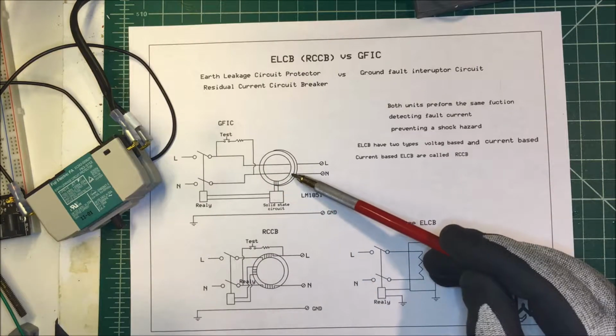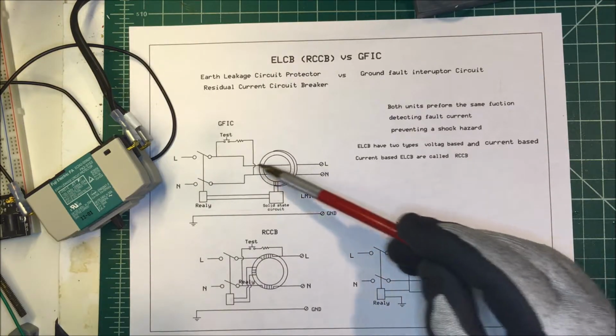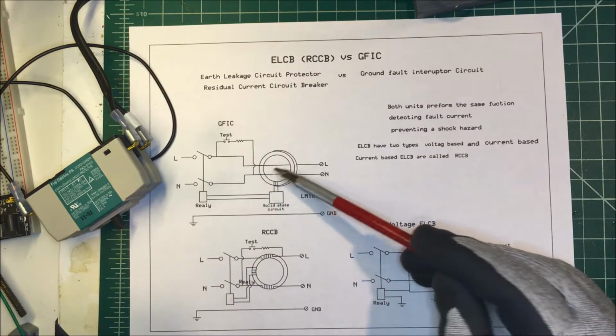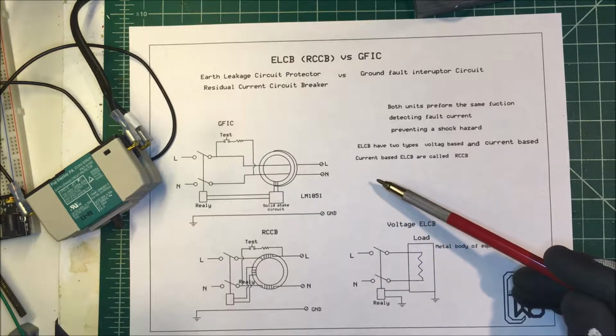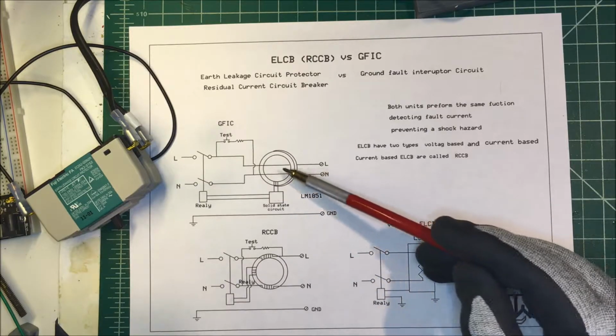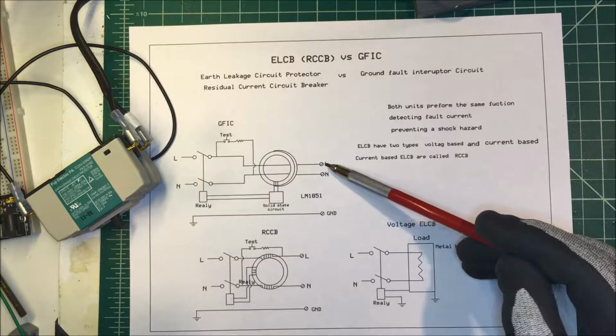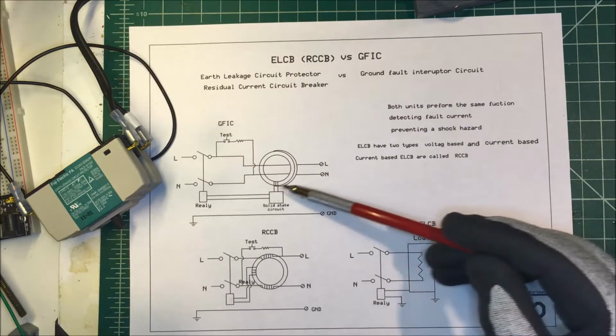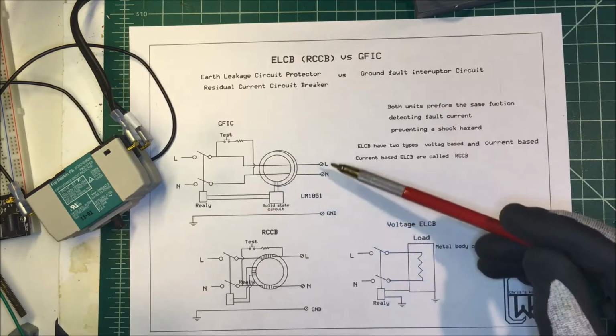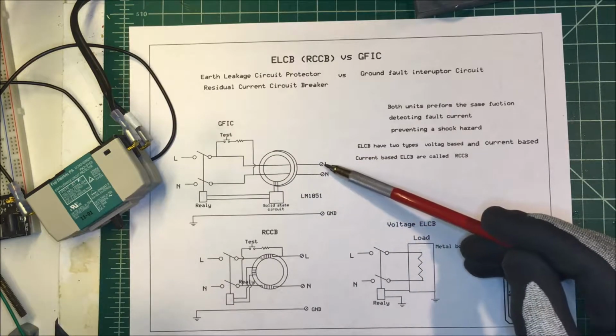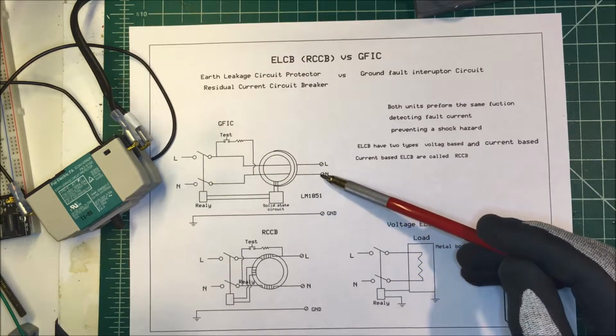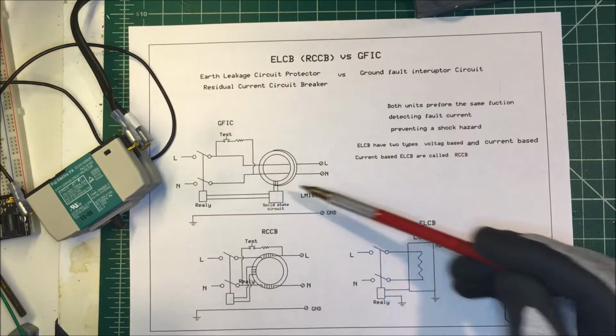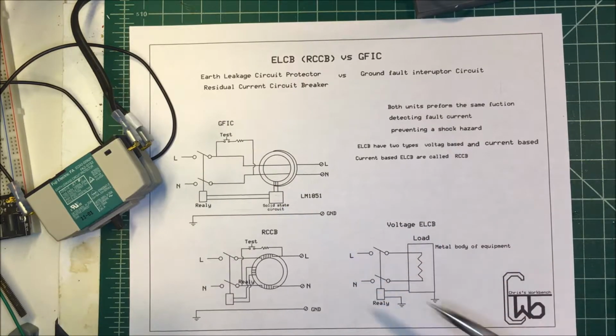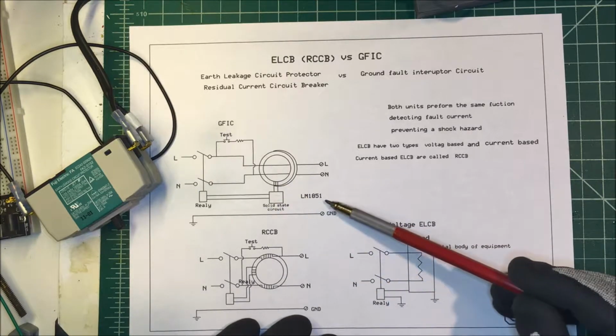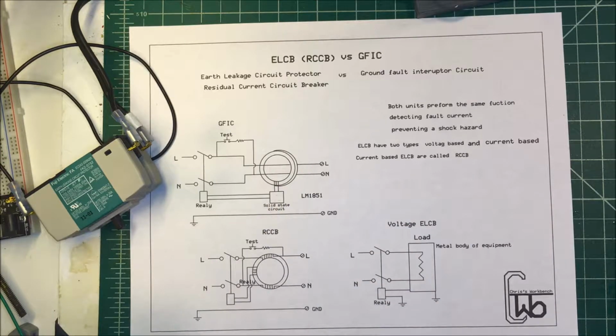This is a GFIC, and what they do is they take both line and neutral and they just run it through the center of the coil. And same principle though, if the electrons come in this way and they all come back this way, they'll cancel each other out and won't produce a magnetic field. But if some happen to go to ground, then there'll be an unbalance and it'll be able to be detected by the solid state circuit here.